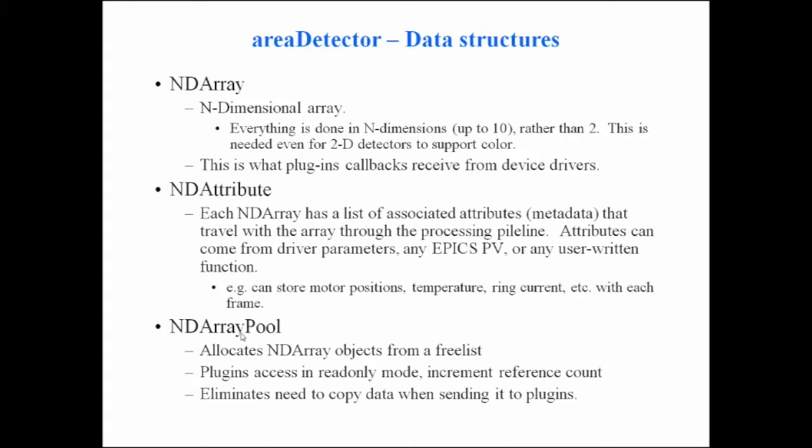Attributes can get their values from driver parameters — like binning or exposure time — or from any EPICS PV. If you assign an attribute an EPICS PV, it puts a monitor on that PV, and every time it gets the attribute value, it gets the latest value of that PV. So your array can have associated with it the ring current and the positions of all motors at the instant it was collected, traveling through the pipeline with it.